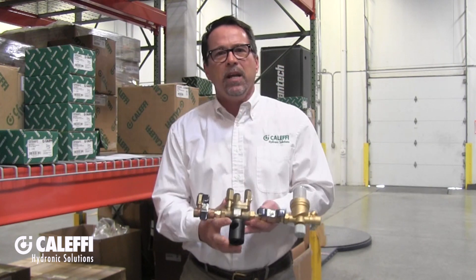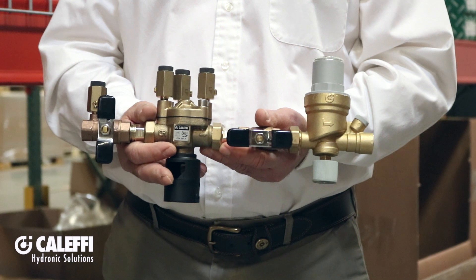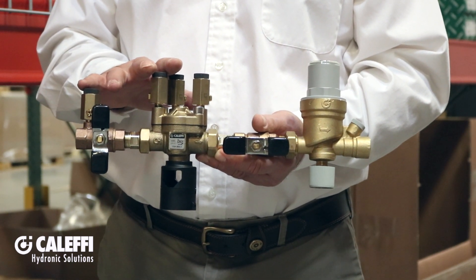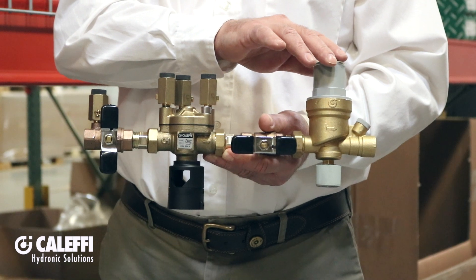For filling and maintaining pressure in these applications, Caleffi offers the 574 autofill combo. The combo consists of the ASSE 1013 backflow preventer, which provides the required backflow prevention, connected to an autofill valve, which adds the makeup water as needed to maintain system pressure.